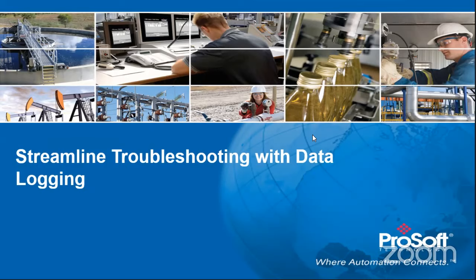Actually, density is one of the process inputs on liquid measurement. Okay, so we'd have to measure. You could enter that through the process inputs. I just remember on our water measurement, in the PLC, they weren't pulling that value from any instrumentation. They used a hard-coded value, I think 737 or something, and we just put that into the PLC and it used it that way. So for something like ethylene, you would just look up what the value is for that, if you didn't have a live density as a process input. If you did have a live density off of something like a Coriolis, then that becomes a process input value. Yep.